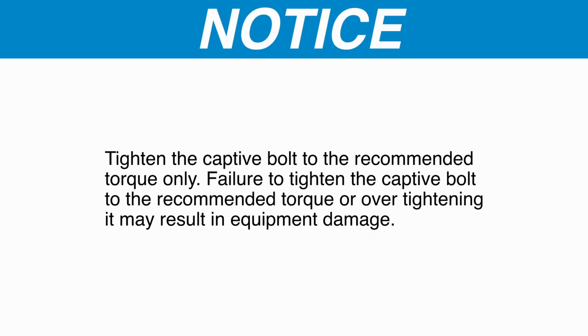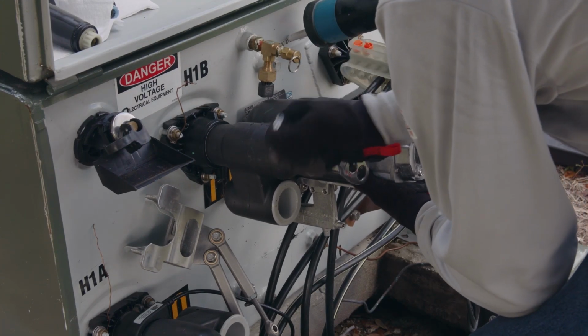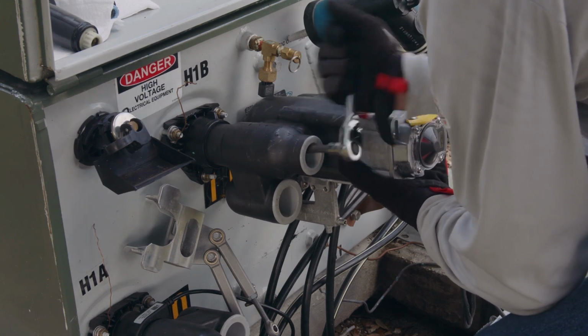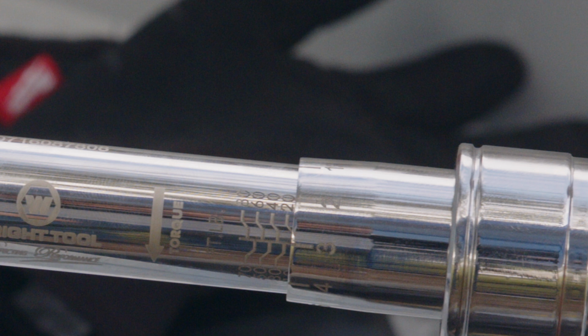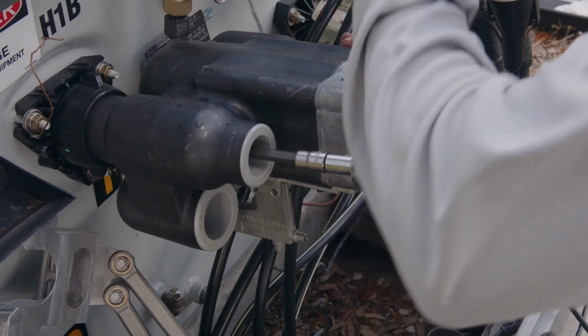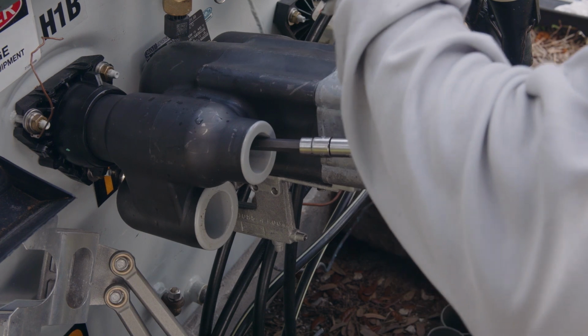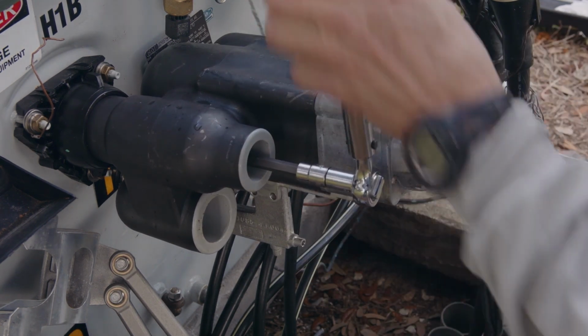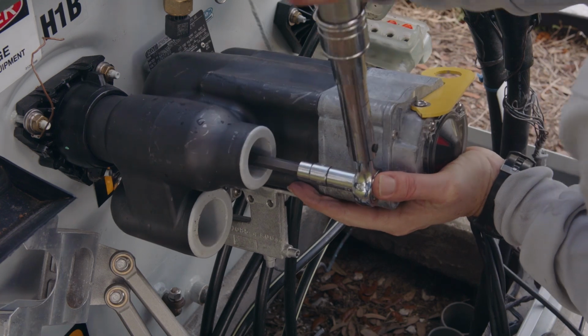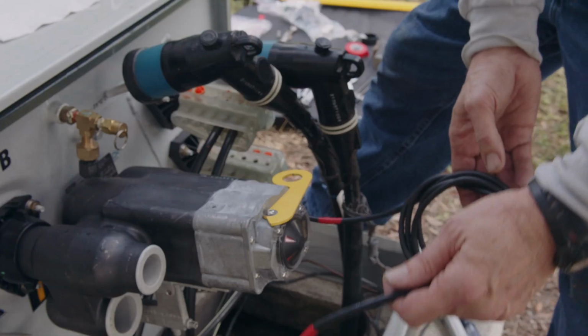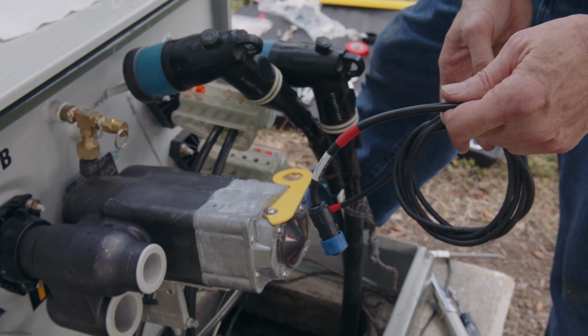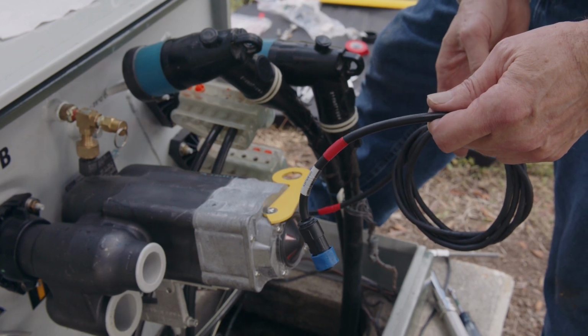well adapter. Notice: tighten the captive bolt to the recommended torque only. Failure to tighten the captive bolt to the recommended torque or over-tightening it may result in equipment damage. Step 3. Tighten the captive bolt using a 3/8" long style Allen wrench to a torque of 23 ± 2 foot-pounds. Note: the weight of the H1B bushing well interrupter may cause it to rotate slightly. This rotation will be corrected when the support struts are installed. Note: there is a red band on the H1B control cable to help differentiate the cables when making connections to the control.